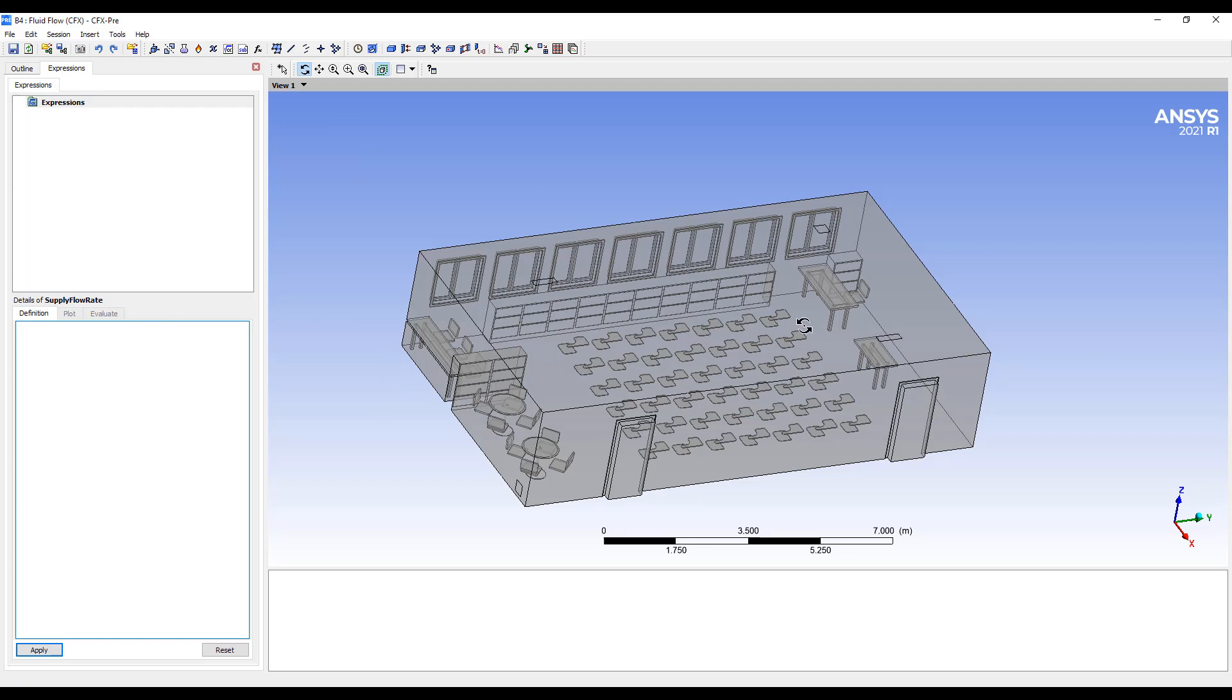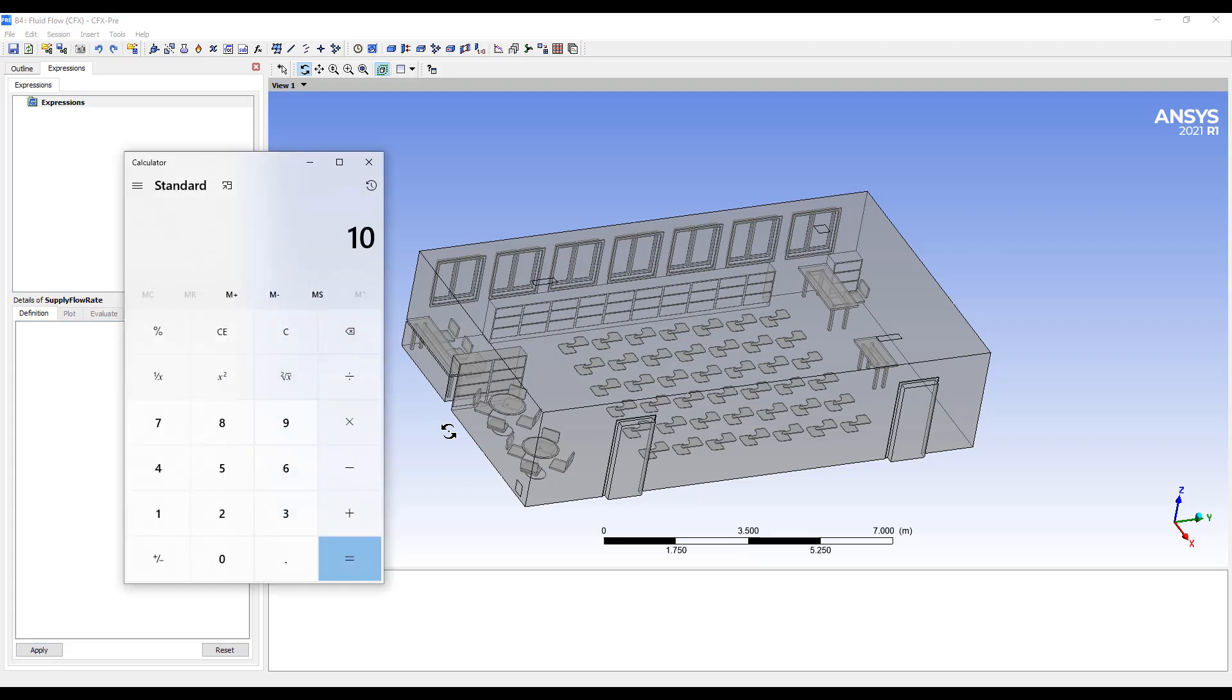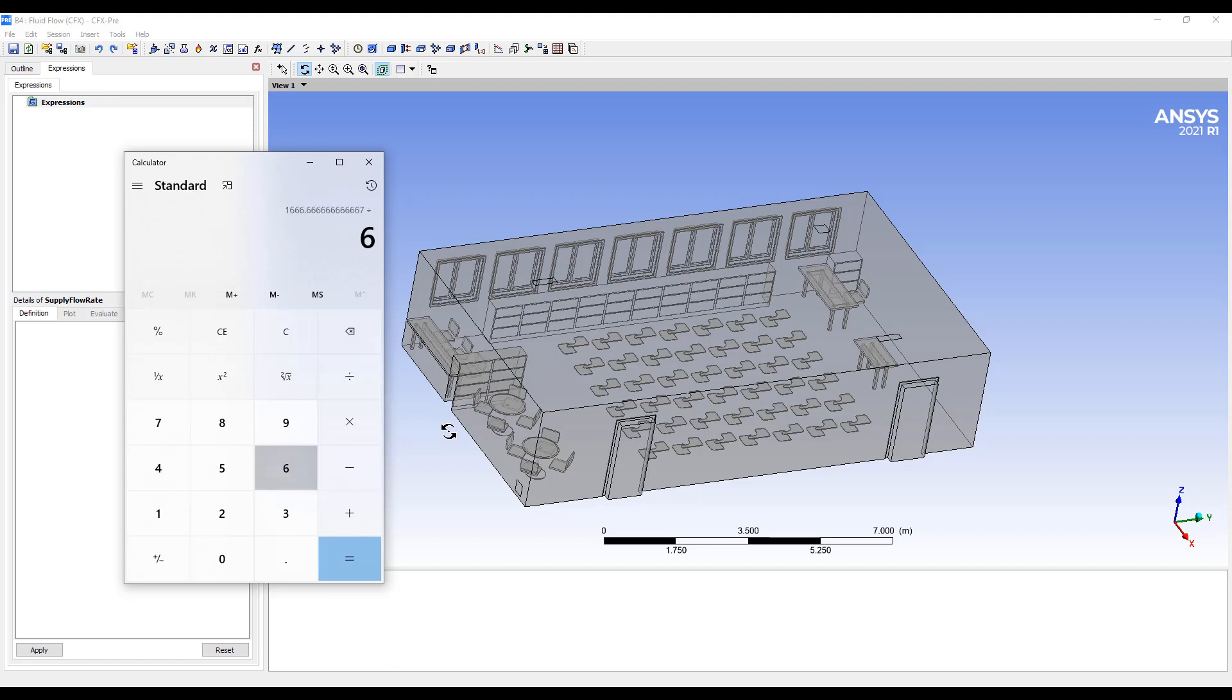It's a thousand square feet, 10,000 cubic feet room. And if we want an ACH of, let's say, six or seven, we can do 10,000 cubic feet, multiply it by six, divide it by 60.